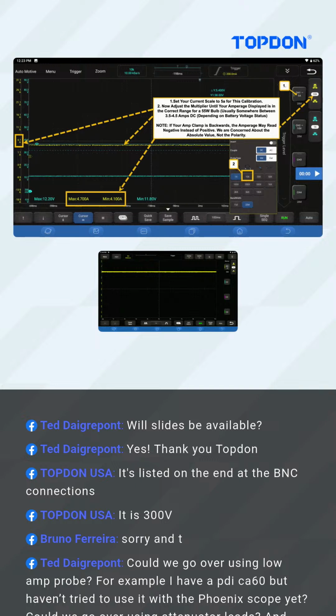Being able to anticipate the normal range for a given component you're connecting to, say a pressure transducer, is important - any product or probe you buy, whether an amp clamp or pressure transducer, typically comes with a manual providing that conversion rate. It should tell you the output of that particular sensor, like 100 millivolts output equals 1 amp or 10 amps, something like that. They should provide that information, but this method I've shown makes it a little easier if you're using a current clamp to understand what you need to do.